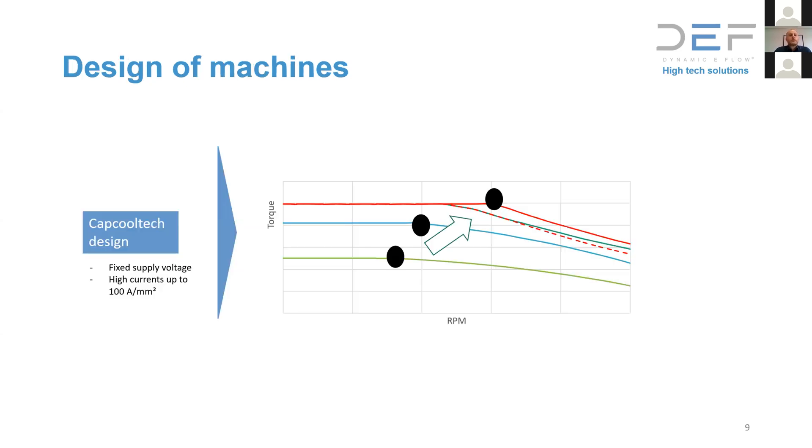This technology also enables moving the base speed point of the electric motor. We cannot change the physics, but because you can set the rated speed at a higher level — which would normally reduce torque — we can compensate by increasing the current since thermal limits are no longer a constraint. If the supply voltage and volume are given, moving the base speed point to the right for a permanent magnet motor also increases the overall achievable power quite a bit.